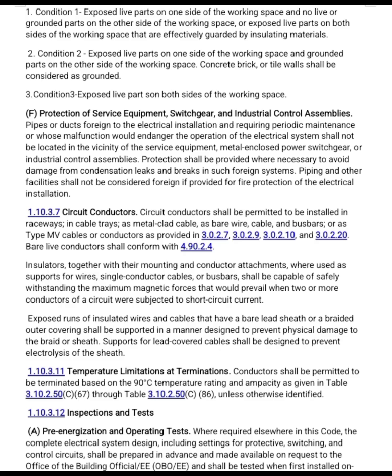1.10.3.7 Circuit conductors. Circuit conductors shall be permitted to be installed in raceways, in cable trays, as metal-clad cable, bare wire, cable, bus bars, or as Type MV cables or conductors as provided in 3.0.2.7, 3.0.2.9, 3.0.2.10 and 3.0.2.20. Bare live conductors shall conform with 4.90.2.4. Insulators, together with their mounting and conductor attachments, shall be used as supports for wires.